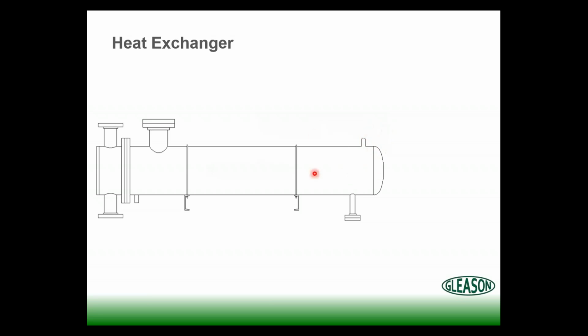The first thing we look at on heat exchangers is this: let's say we've got steam coming to the heat exchanger and we shut the steam off to that unit. At 1,600 times volume, it reduces to 1 as that steam condenses. So it reduces to 1 and it pulls a vacuum on the unit. It's just like putting your finger over the end of a straw, pulling it out of your soft drink. We're going to be holding liquid in that straw. And that's exactly what can go on in these units.